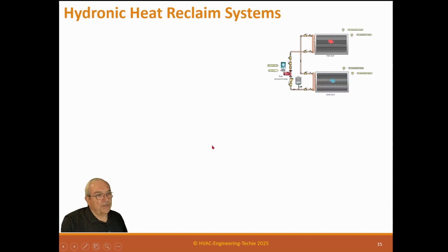So now we'll look at another system, which is a hydronic heat reclaim. We use these in air systems where we have a whole lot of outside air or a high changeover of outside air, and we want to take the energy out of the exhaust air and move it back into the outside air. So we recapture some of that energy, whether it's heating or cooling. These are the systems that have a big coil, and this is a water circuit with a pump that runs the water between these systems. And it takes the energy from the hot coil and moves it to the cold coil, whatever they are.